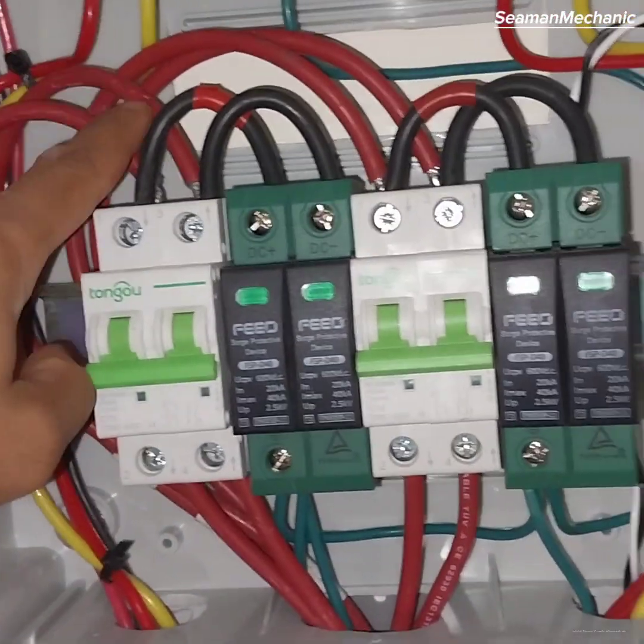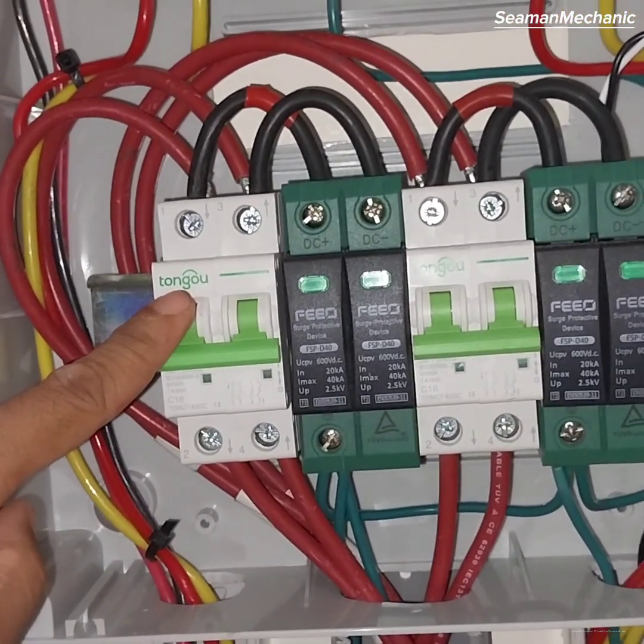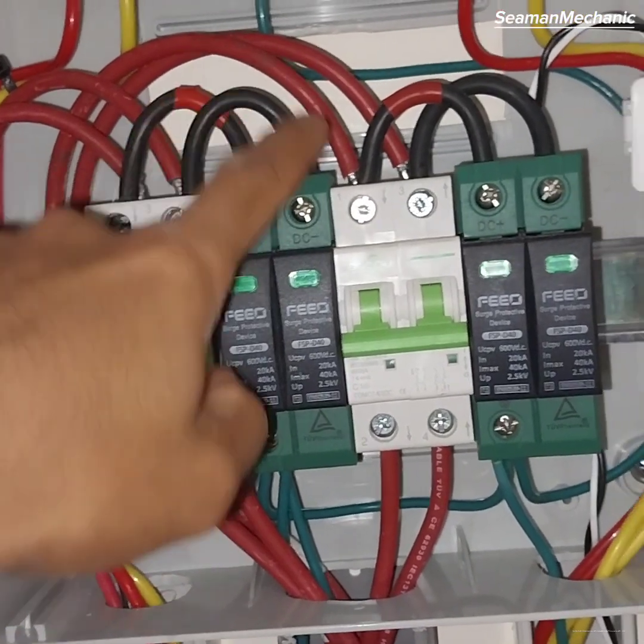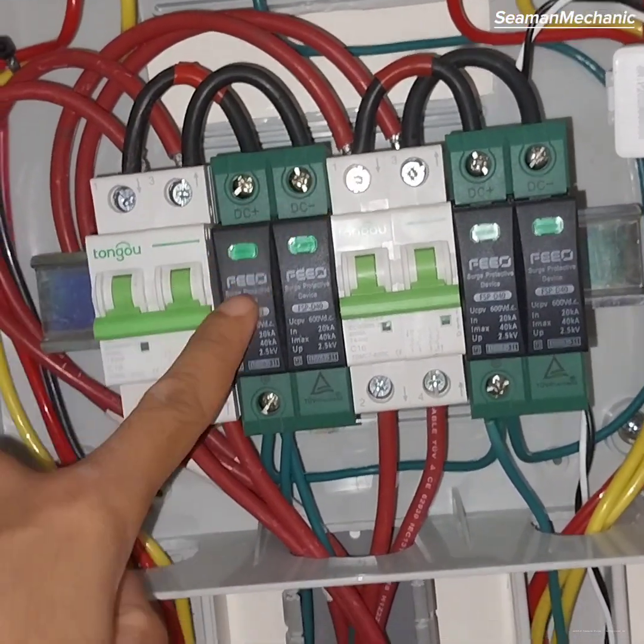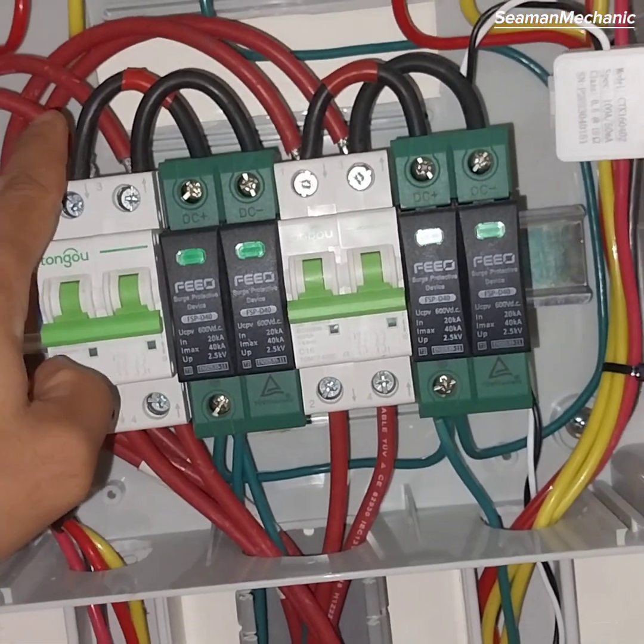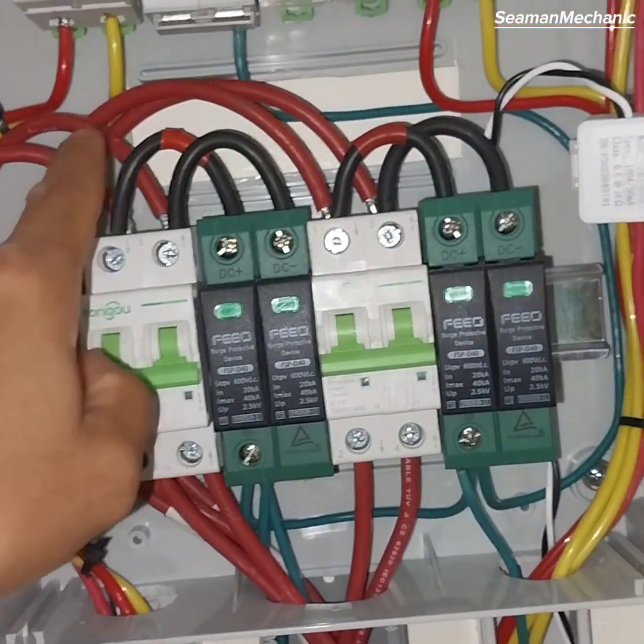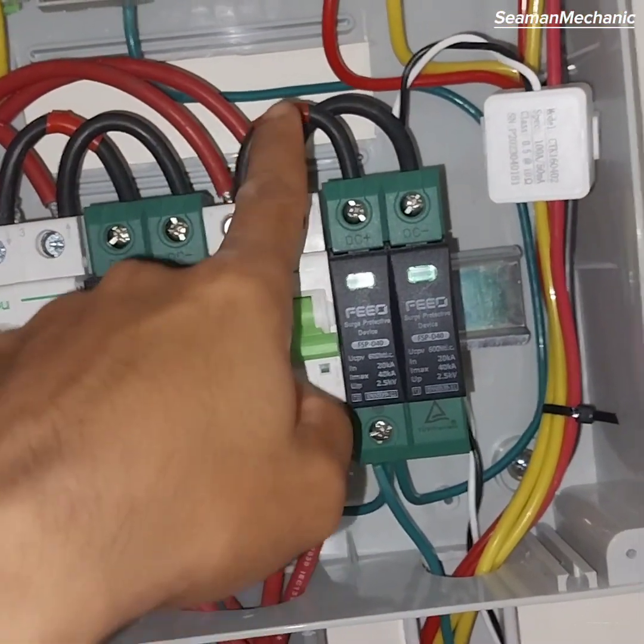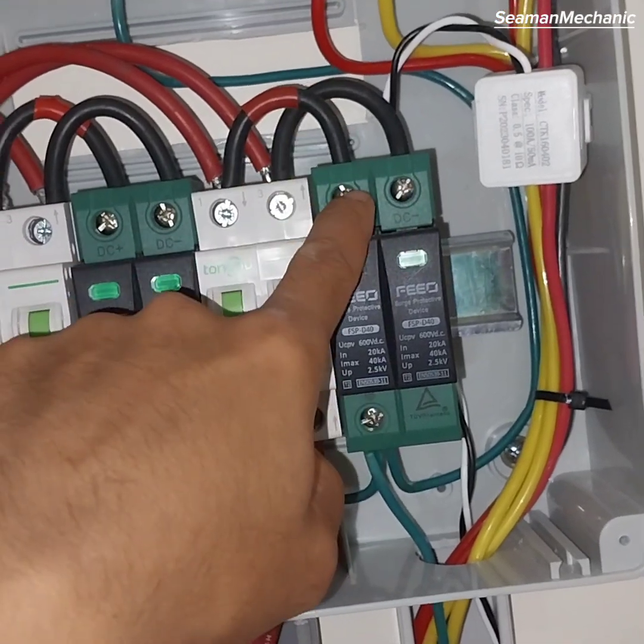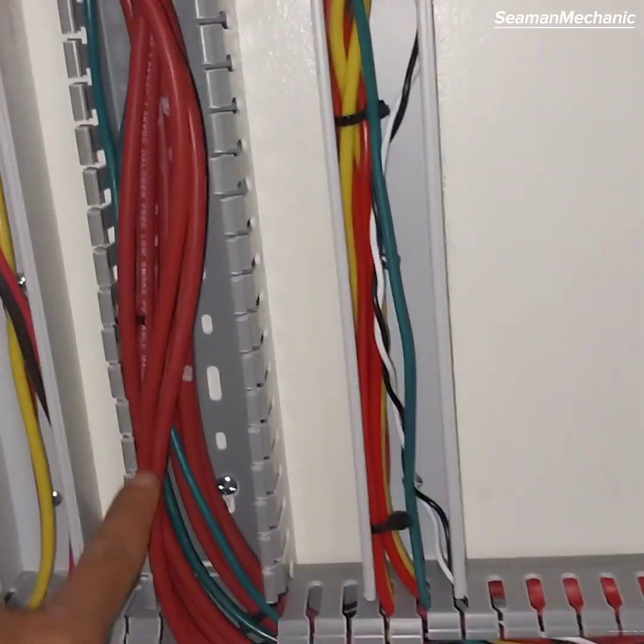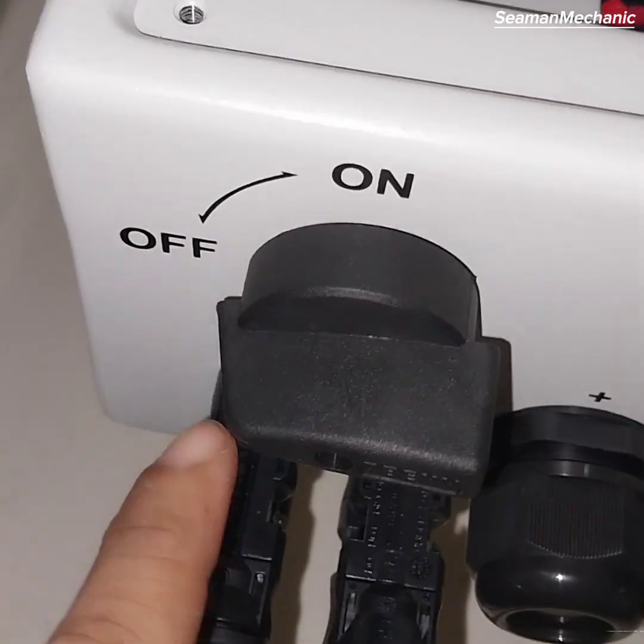Then into DC circuit breakers and SPD or surge protection device, connected in parallel. Each PV string, string 1 and string 2, has its own DC breaker and surge protection device. From DC breakers, it will go into isolator switch and inverter to convert DC electricity to AC or alternating current electricity.